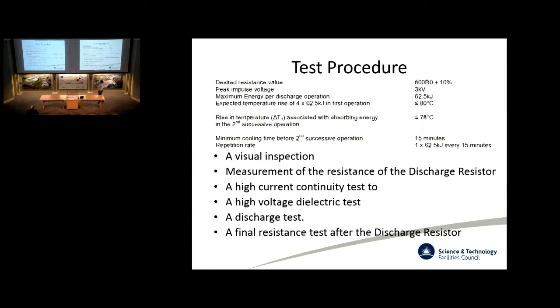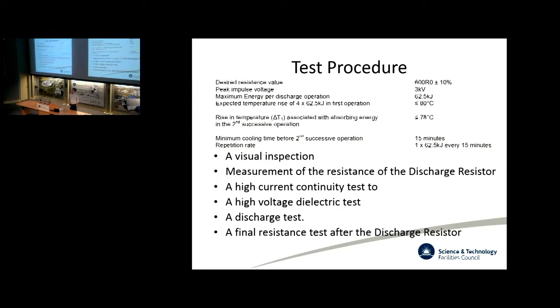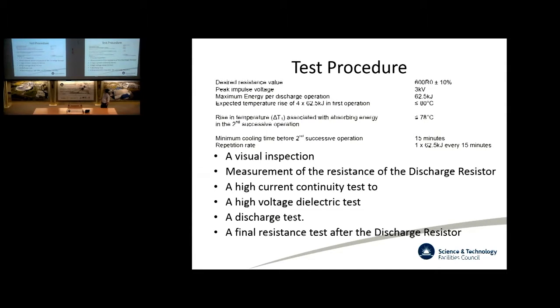We perform a visual inspection of the stick to make sure that there are no apparent breaks or rips or anything like that. We measure the resistance of the resistor, and in most cases it's tens of ohms up to maybe hundreds of ohms. This is so that when you use the stick in anger, you don't get a massive fault current, as you would if you just stuck an earth straight on a charged capacitor. You're going to get many thousands of amps possibly travelling through that earth. So we use a resistor to restrict that current.